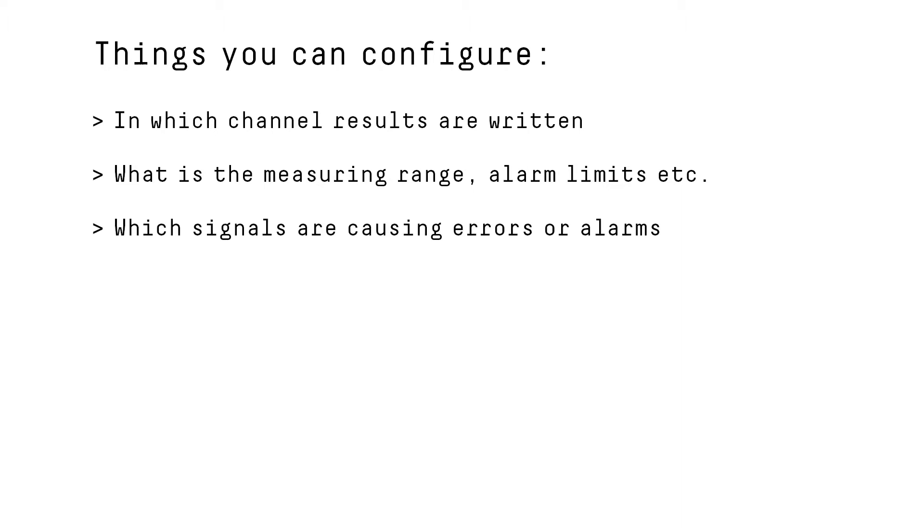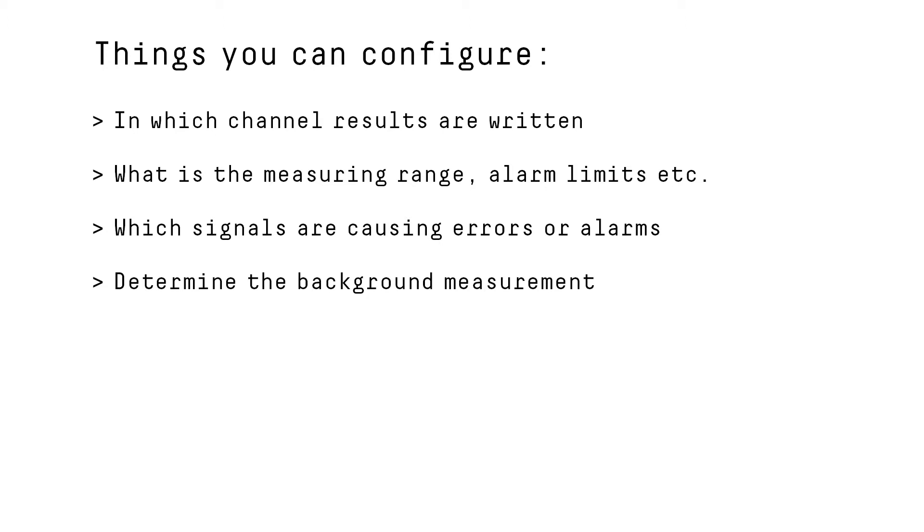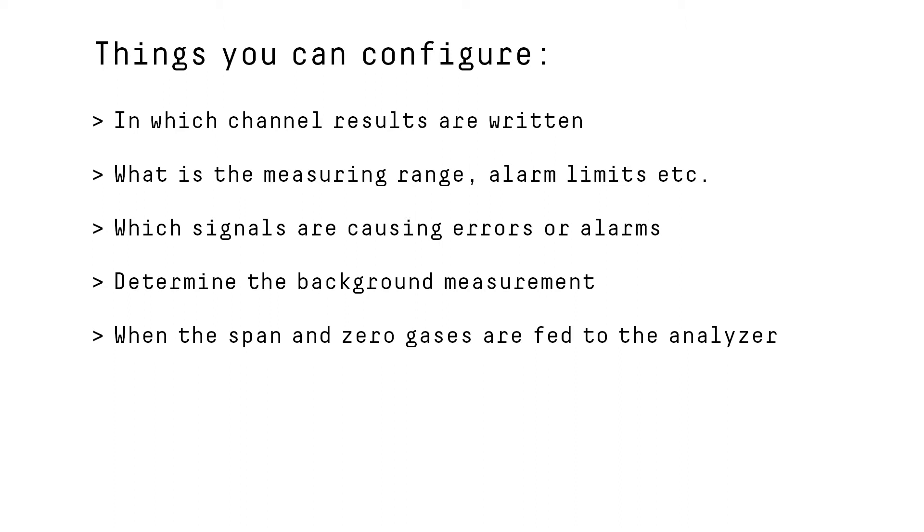What signals are causing a system error and which signals are causing a service request. You are able to determine when the system is making the background measurement, when the span and zero gases are being fed to the analyzer to check the measurement accuracy, how long is the flush time and so on.